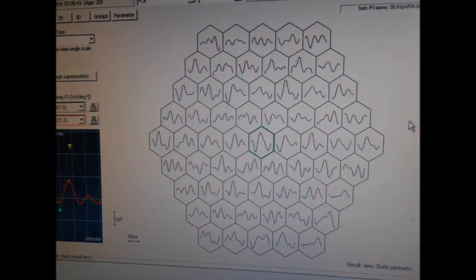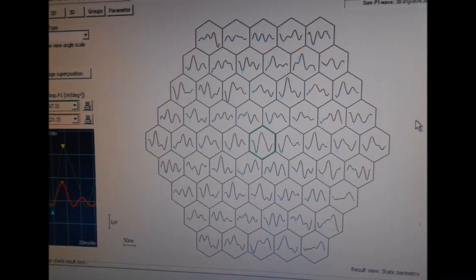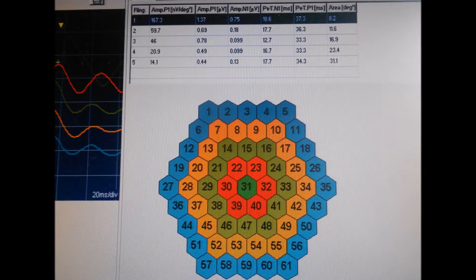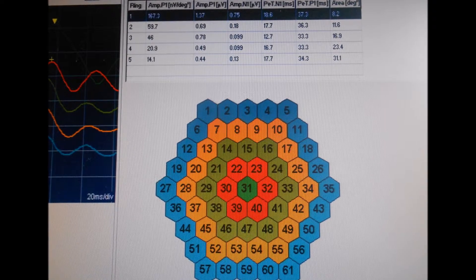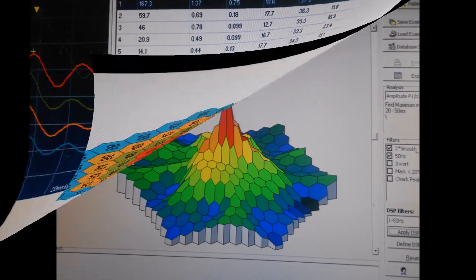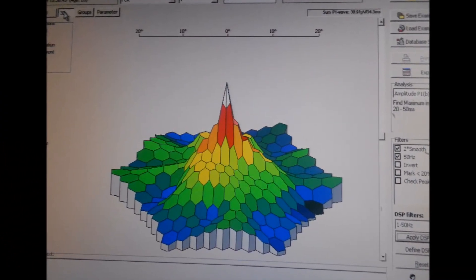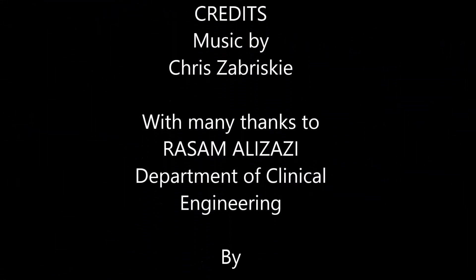The scalar product is used to determine the response of the MFERG. The scalar product is obtained by multiplying the corresponding template waveform points with the recorded waveform, and adding the multiplication results to obtain a single result. These values are then divided by the hexagonal area to acquire the topographic plot.